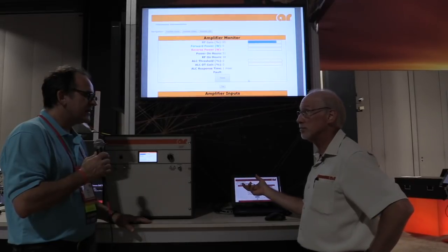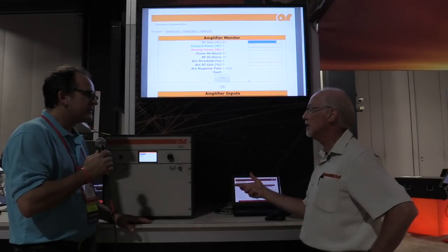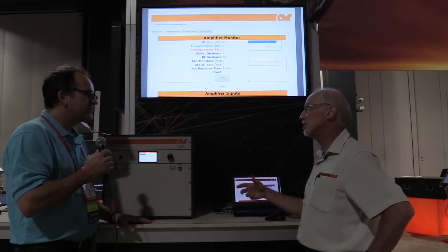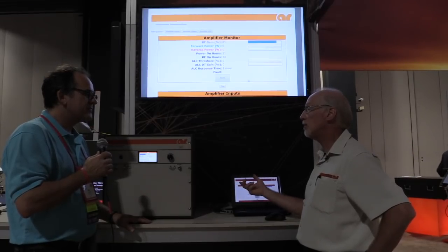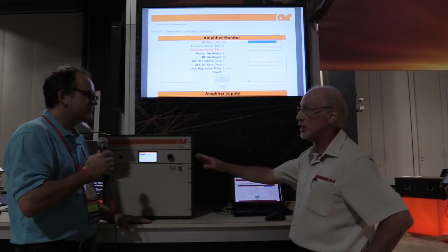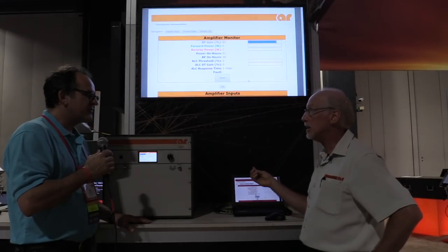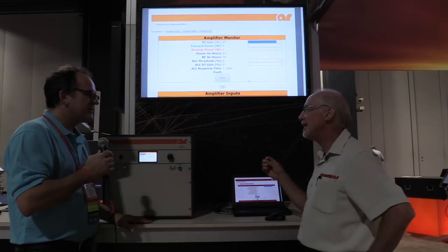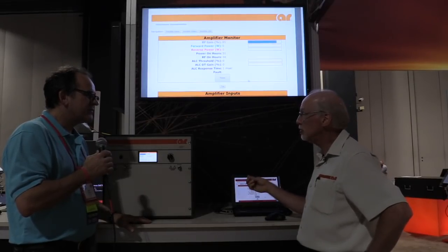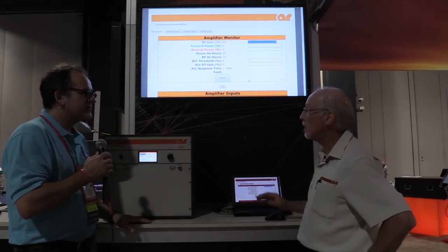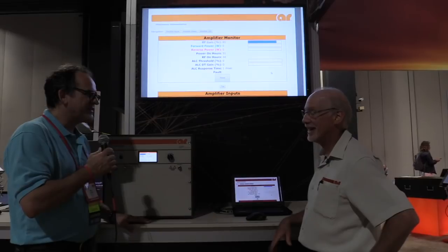data logging. So you can now monitor over time the health of the amplifier. Maybe give yourself notification of when the amplifier needs service, how often it's being used. And some of the large amplifiers are a good sized capital expense for any company. Sure, I'd like to know, am I getting optimal use of that amplifier, that capital asset? Is it in use as it should be? So I can monitor that right here. So you've got an online Hobbs meter, basically. Correct. You can see that.